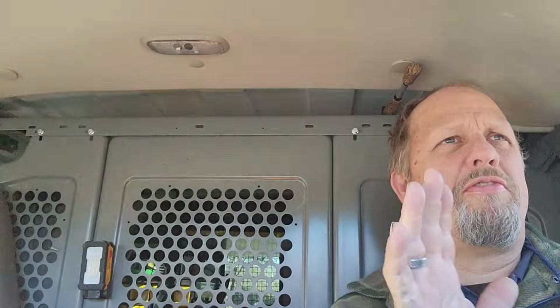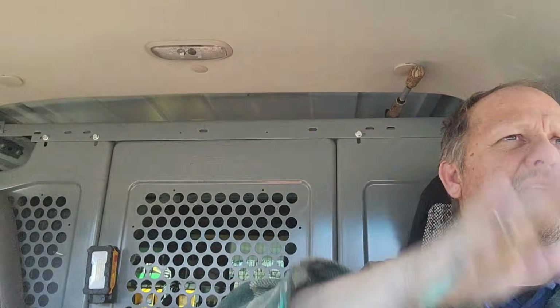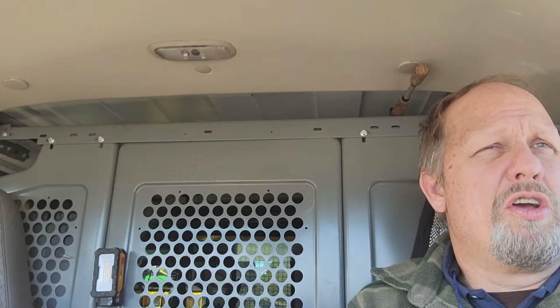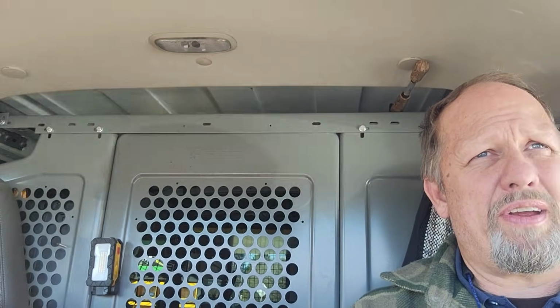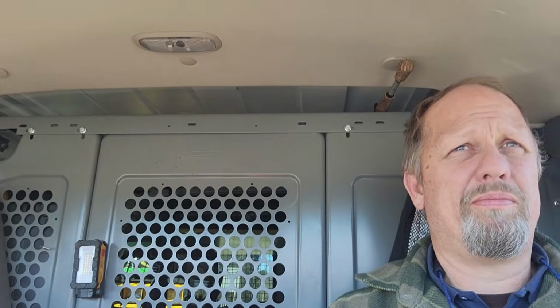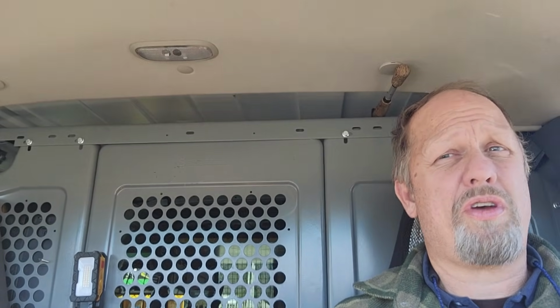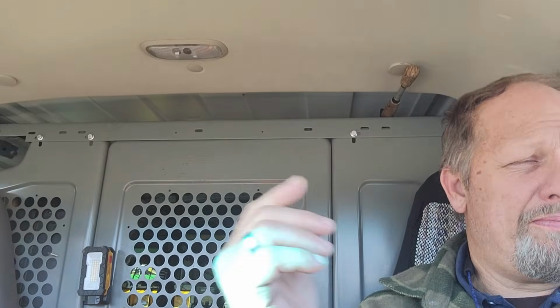They had just set the filter on top of that 12-inch return instead of having it in the grill. I see this a lot, people just cover the hole with the filter. There was a circle of dirt on the filter, and it was 100% dirty, so I knew it had been starving air for a while. That was the first thing I saw, Wes.